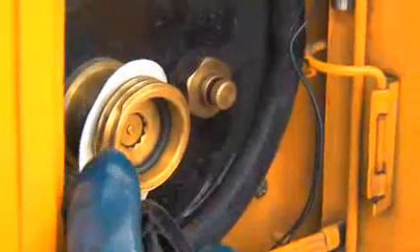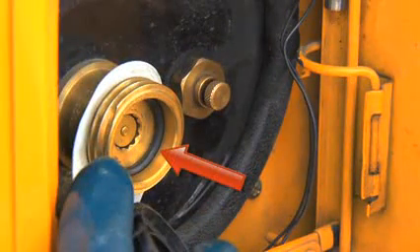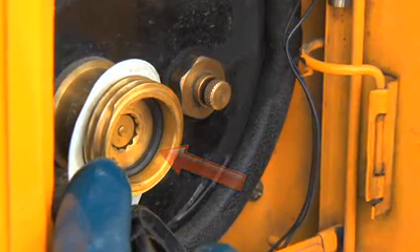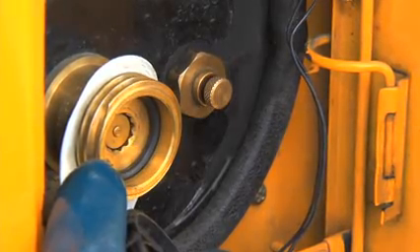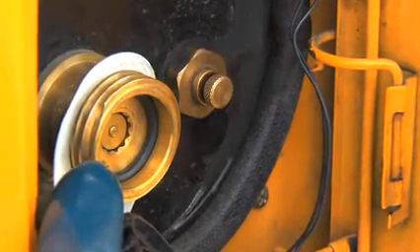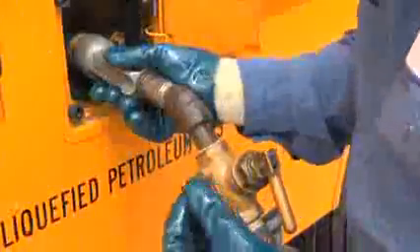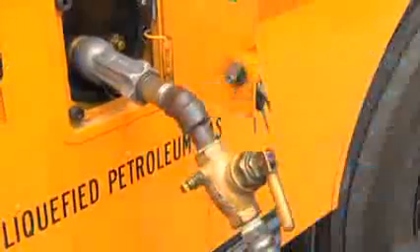Take a look inside the filler valve. Make sure the O-ring in the filler valve is seated in the groove and is not damaged or missing. Never connect the filler nozzle to the filler valve if the O-ring is missing or damaged. This could result in a release of propane with a potential for injury or fire. Connect the propane filler nozzle to the filler valve and rotate the filler valve nozzle clockwise until it is firmly attached. Be sure the filler nozzle vent valve is closed if equipped.